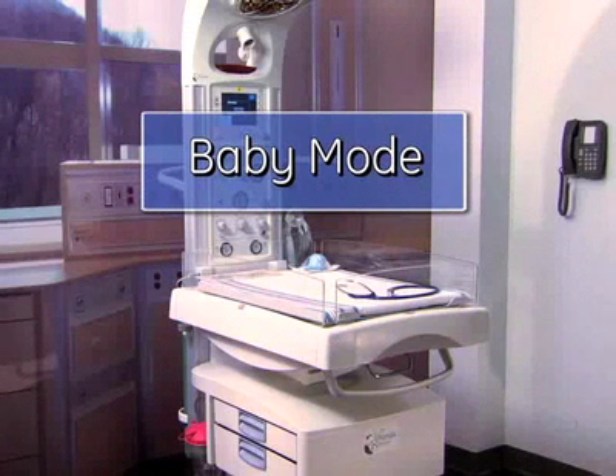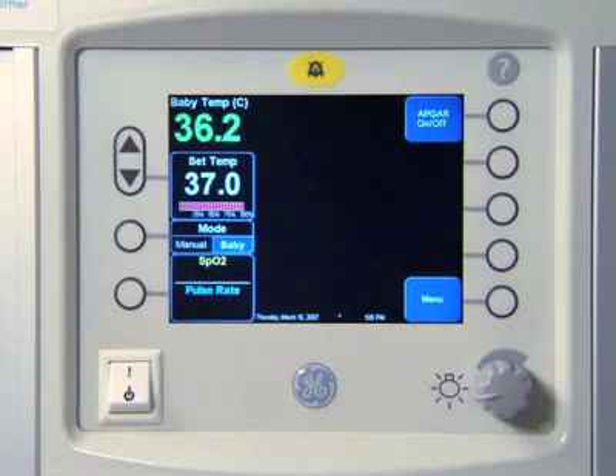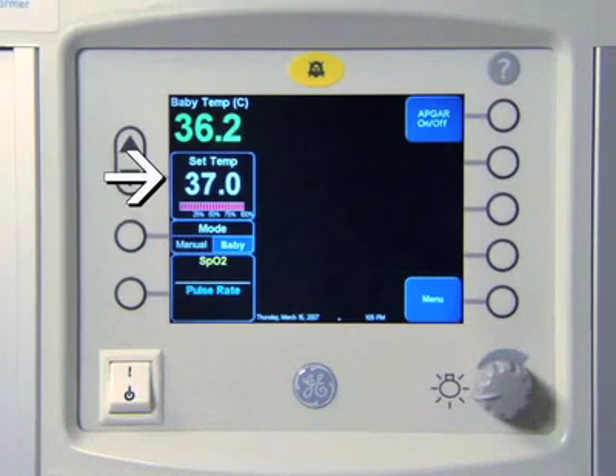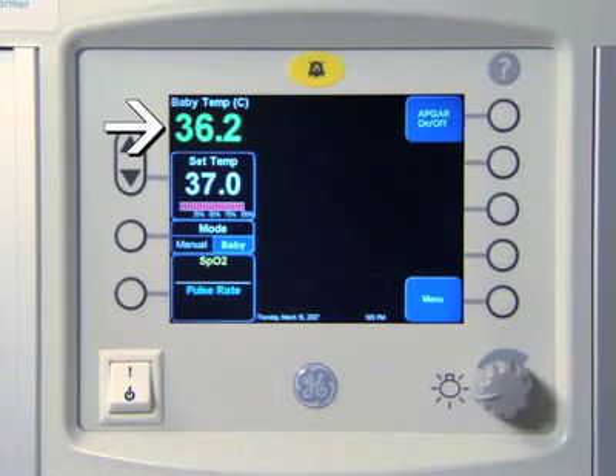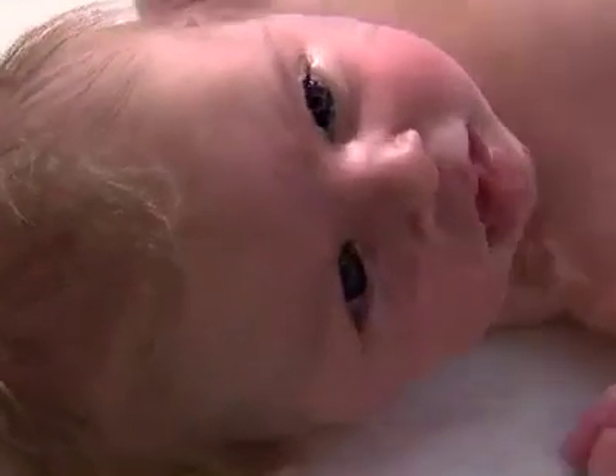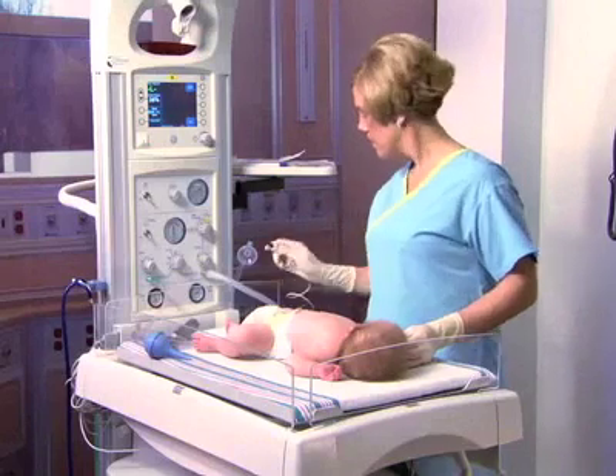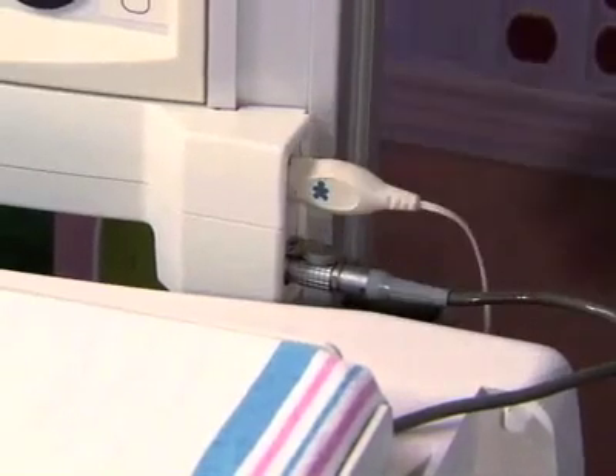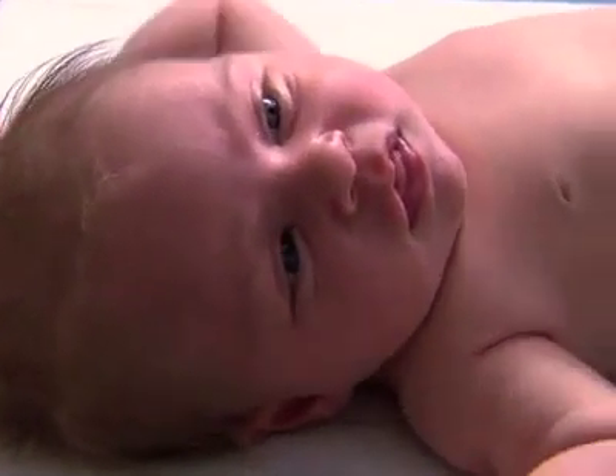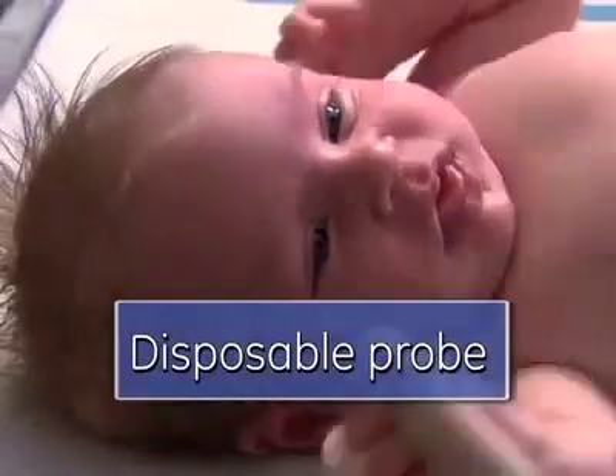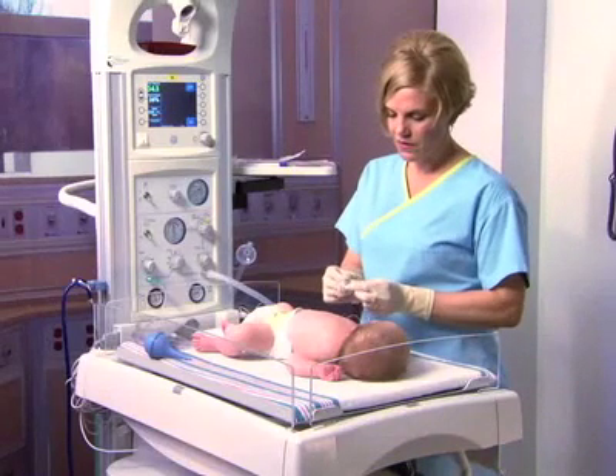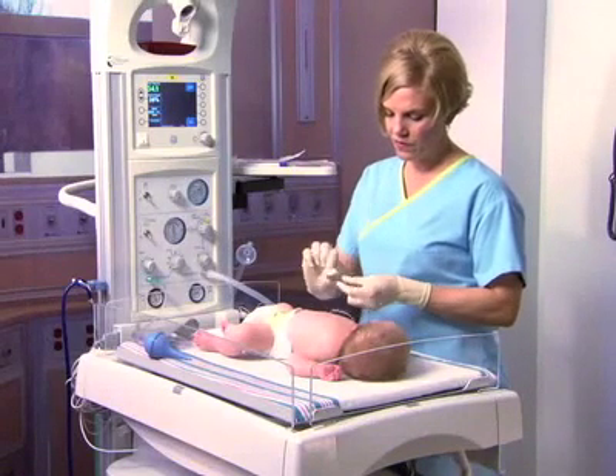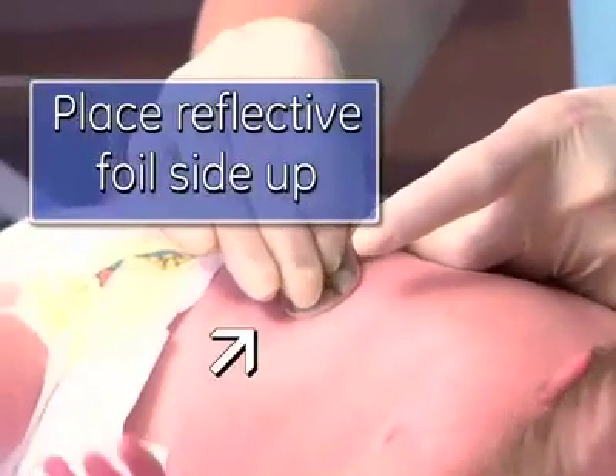In the baby mode, the warmer controls heater output to a desired baby set temperature you enter. Heater output is based on measured differences between the set temperature and the skin probe temperature reading. To place the temperature probe on the baby, first insert the temperature probe into the probe jack connection on the side. Make sure the baby's skin is clean and dry before applying the probe. To attach the disposable probe, peel the paper backing from the adhesive side and apply to the baby's skin with the reflective foil side up.